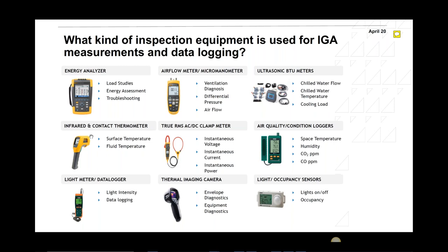So none of those. A BTU meter will only help us check, let's say, chilled water systems. The energy analyzer is only for electrical systems. As for the thermal camera, I thought maybe a lot of you would choose it, because I kind of tricked you when I mentioned it. We use it to check whether there is insulation or not. We don't know the value of the insulation. We just see that part of the wall looks a different color than the other part, which means one part has insulation and the other does not.